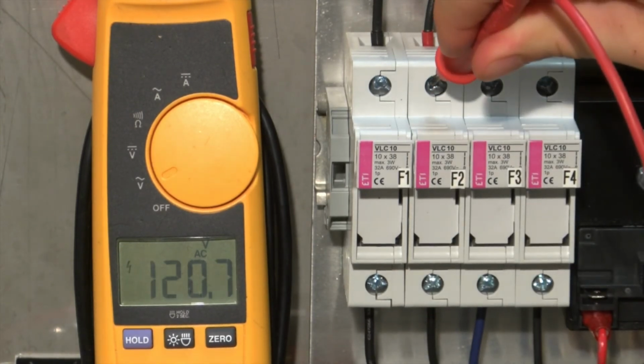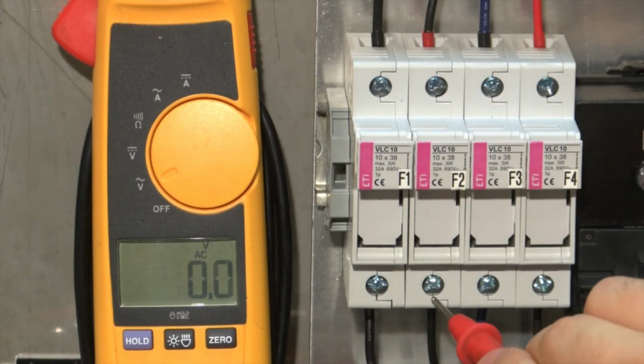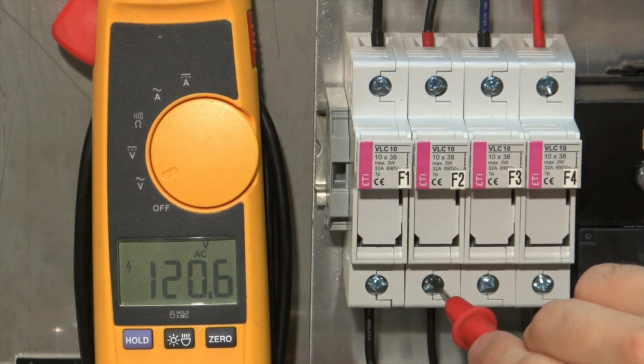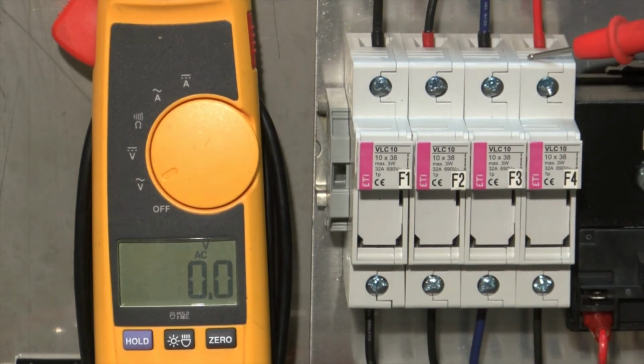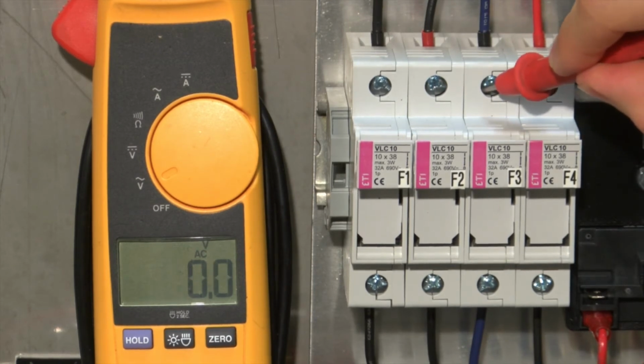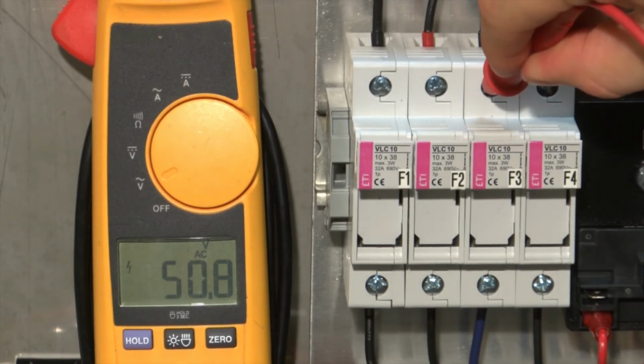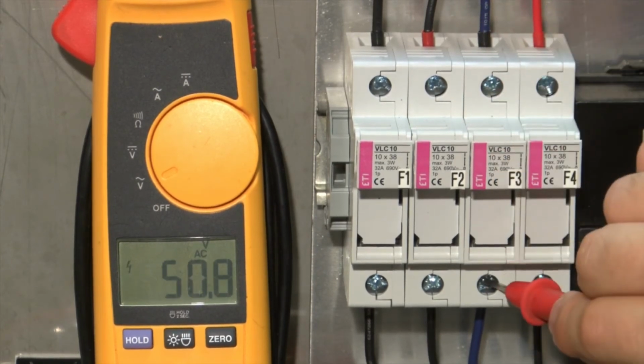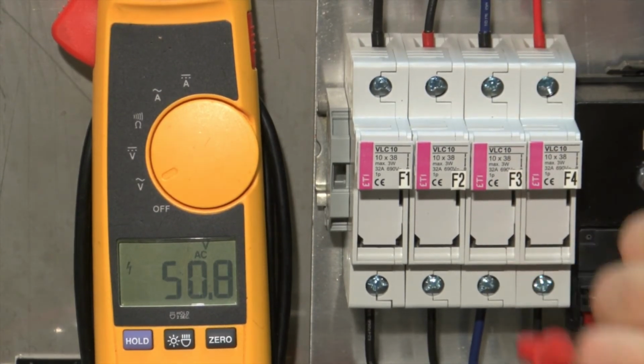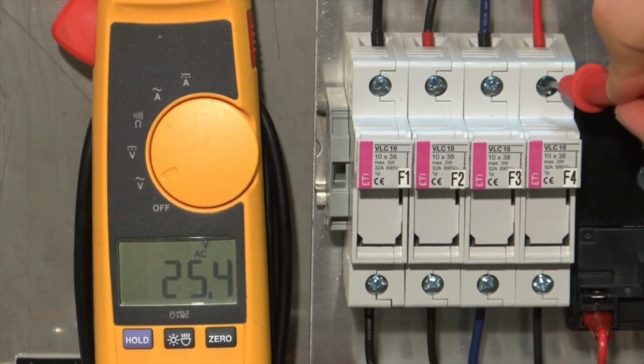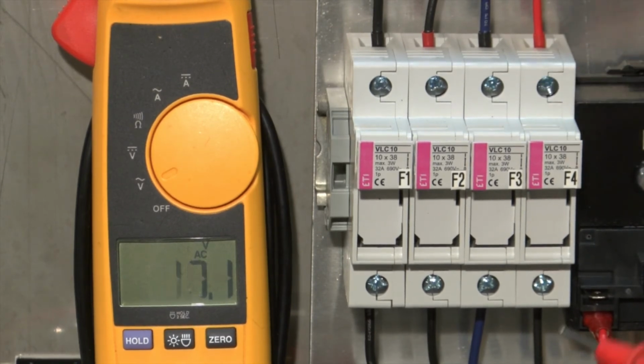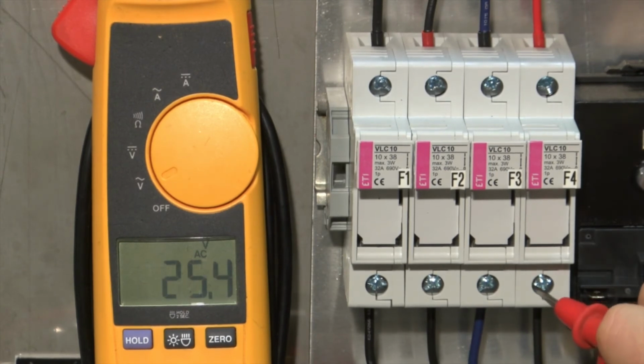On F2, the incoming power is 120. The outgoing power is 120. When checking your secondary fuses, be sure you're using the secondary or orange tap on the transformer to get an accurate reading. In this case, we have one prong on the secondary neutral and can check the 48 volts coming in, the 48 volts going out, and on the 24 volt fuse, we can see the 24 volts coming in and the 24 volts coming out.